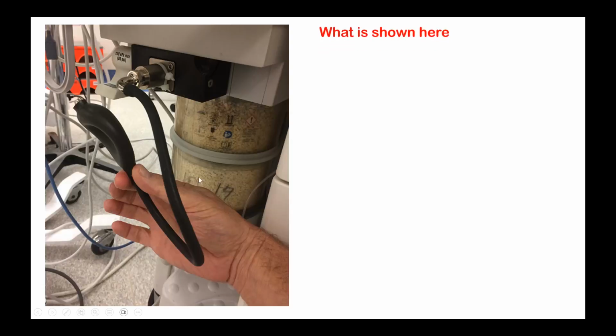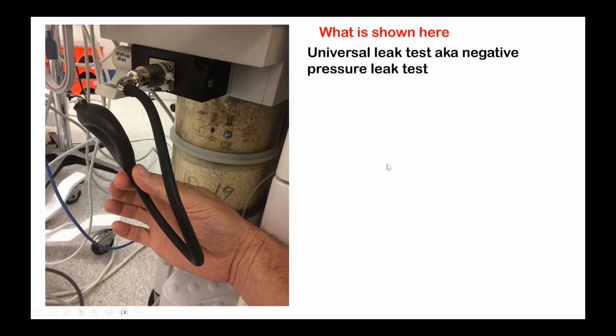These are all the checklist items that we should do. What is shown in this picture? Negative pressure. It's called the universal leak test or negative pressure leak test. So how is it done? It will connect to the common gas outlet, with a tube and a bulb, a suction bulb.